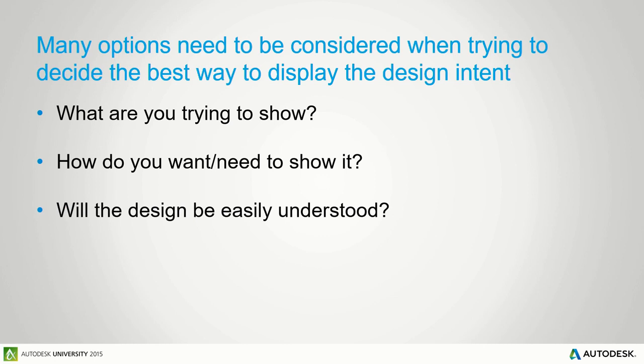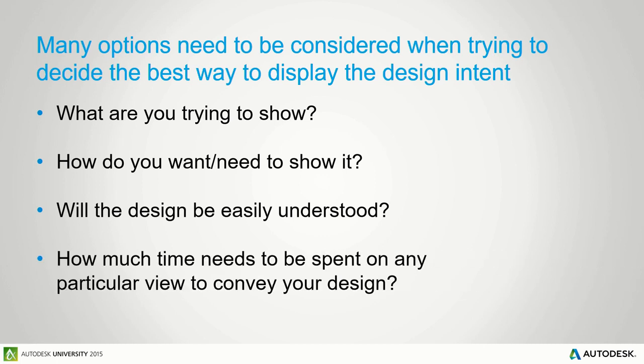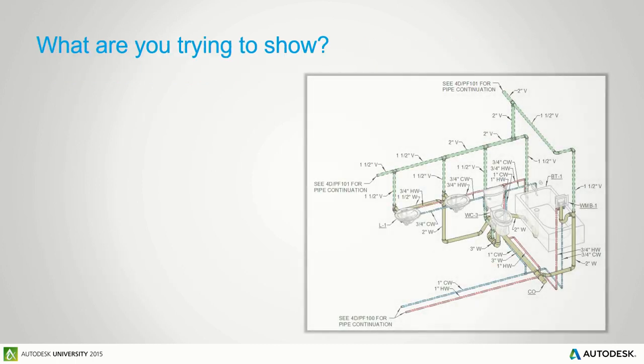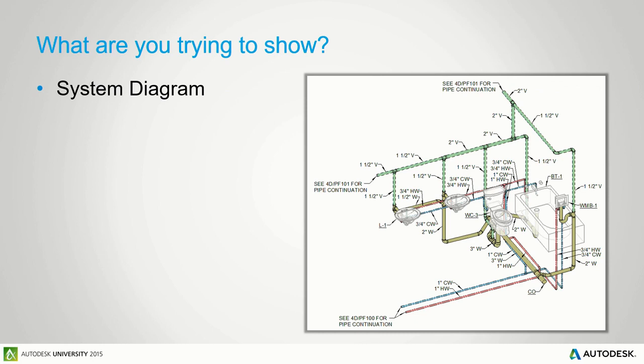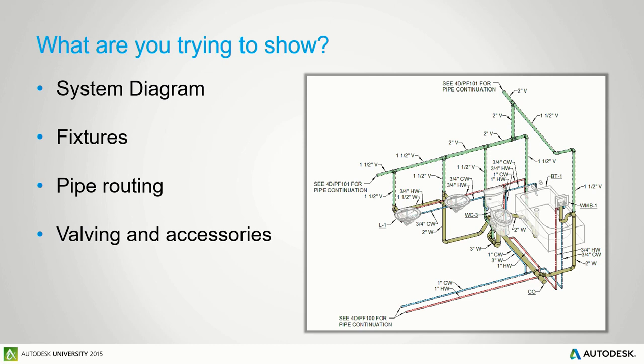Consider whether the design will be easily understood in a plan view versus using an ISO to clearly convey what you're trying to do for a particular system. Also consider how much time needs to be spent on any particular view — is it faster to cram plan notes on an eighth-inch scale plan, or faster to create an additional drawing that has everything on it? For plumbing ISOs, we're looking at the system diagram, overall fixture layout, general pipe routing, valving, accessories, and all the notes and tags that describe the system so it can be constructed in the field.